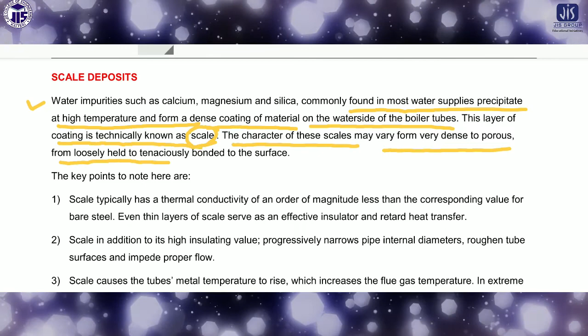Water impurities such as calcium, magnesium, silica, commonly found in most water supplies, precipitate at a high temperature and form a dense coating of material on the water side of the boiler tubes. This layer of coating is technically known as the scale. Actually, this coating is called the scale. The character of this scale may vary from very dense to porous. Either it will be dense or it will be porous, it depends. Okay, so from loosely bonded to tightly bonded to the surface. So it may be loosely bound or tightly bound with the surface.